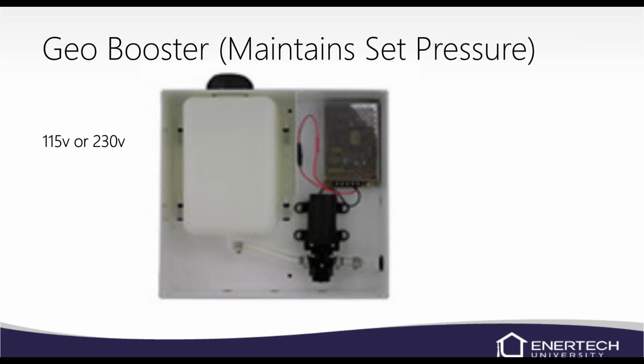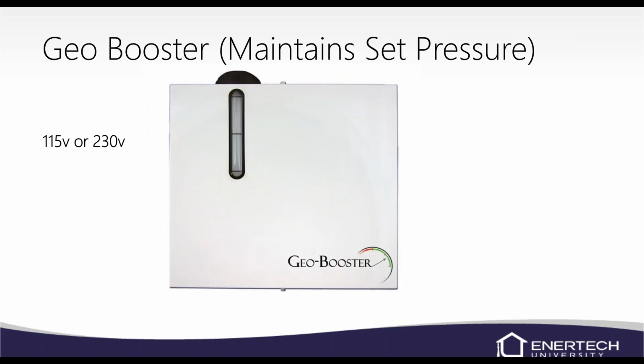What I'd like to do is get a mix of the antifreeze that they have in the system and put it in the tank. Obviously, don't put straight antifreeze in there. And then if you have some extra, just set a jug underneath the Geo Booster and leave it. And like in this last picture here, you've got a sight glass, and if the antifreeze has color to it, the homeowner can see that, and when it gets low, they can just fill it up.